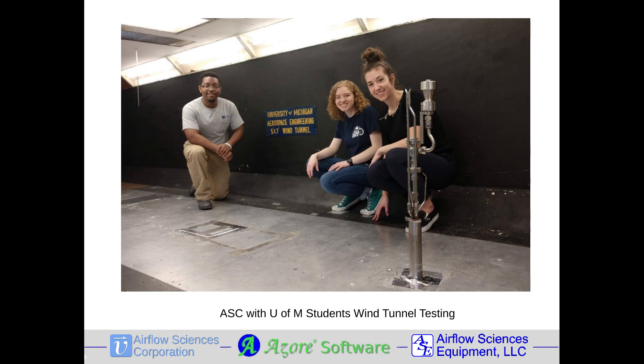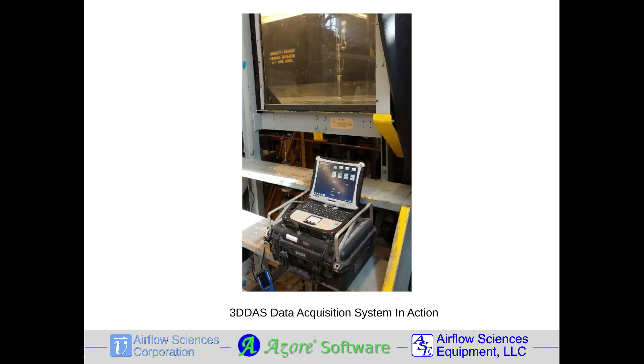A photo taken during the U of M PM10 probe calibration featuring ASC staff and students is shown. Airflow Sciences uses a data acquisition system called the 3D-DAS to perform the calibrations, shown here performing the PM10 probe calibration. This measurement system includes fast response, accurate pressure transducers for probe differential pressure, and also measures important ambient conditions such as barometric pressure, temperature, and static pressure. The 3D-DAS is capable of reading up to 5 pressures simultaneously, so it is used for standard pitot probes with a single pressure signal, or with 3-dimensional pitot probes with multiple pressure signals.